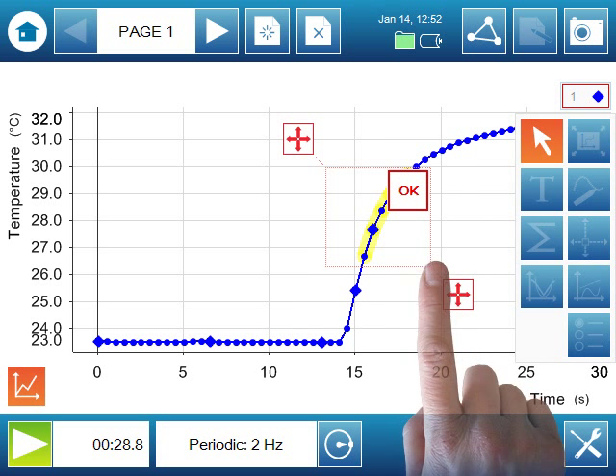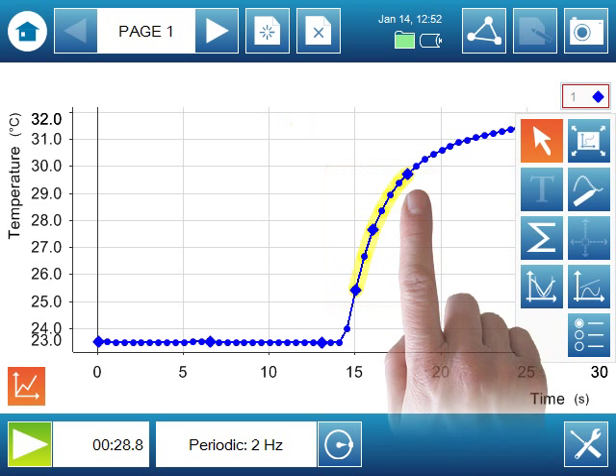Now, sometimes I might be interested in analyzing or viewing just a portion of the data run that I've collected. In that case, I can turn on Select and touch the graph in two places in rapid succession to define a region of interest. I can adjust that region. And now tools such as Scale to Fit will apply just to the selected data points.